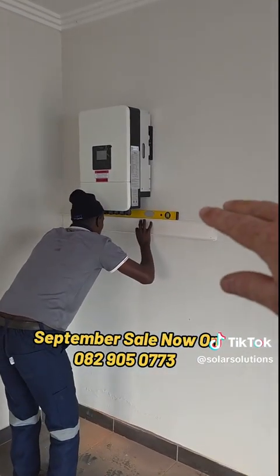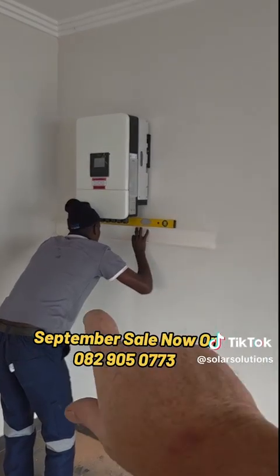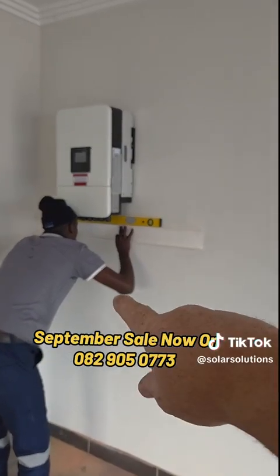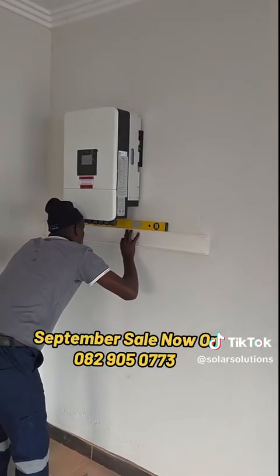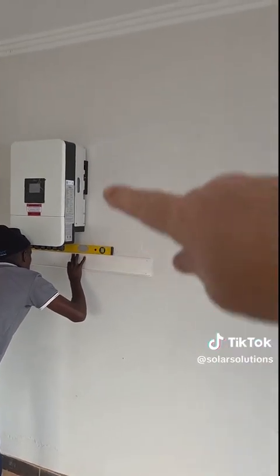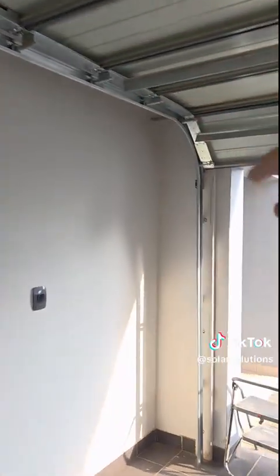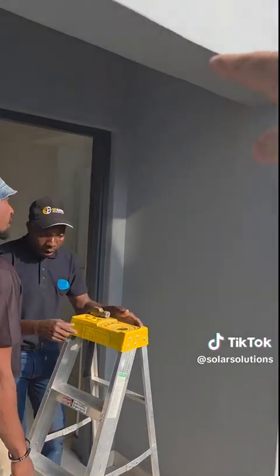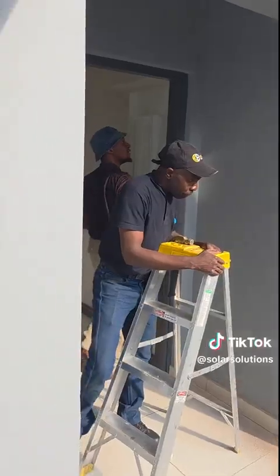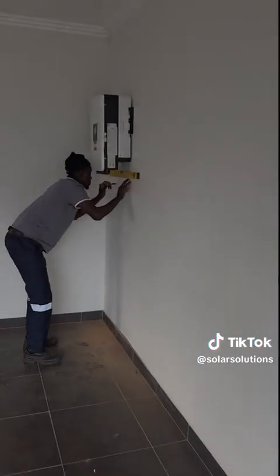So we're going to the front right so the doors won't be an issue, and we'll put the 3 batteries at the bottom there. The 3 batteries will go via a bus bar and a 250 amp battery disconnect. The AC is going to go up and out. The main DB is just behind this wall, so we're busy drilling through the walls. It's underneath the staircase, so we're running the AC cable that way, with DC cables on the left.